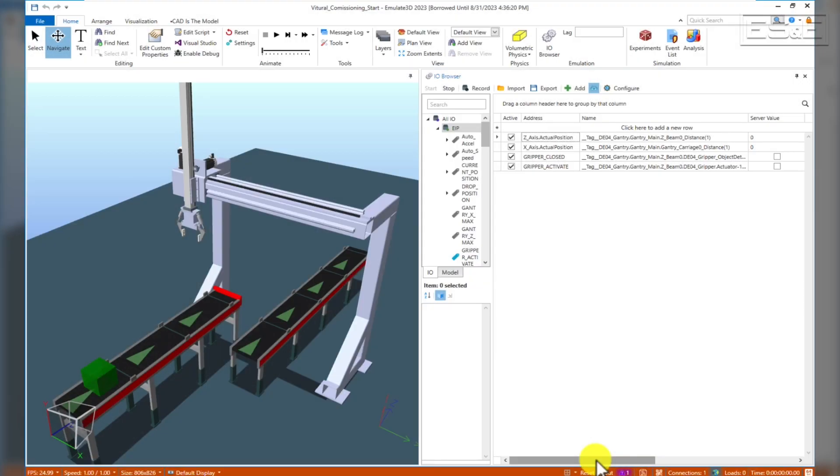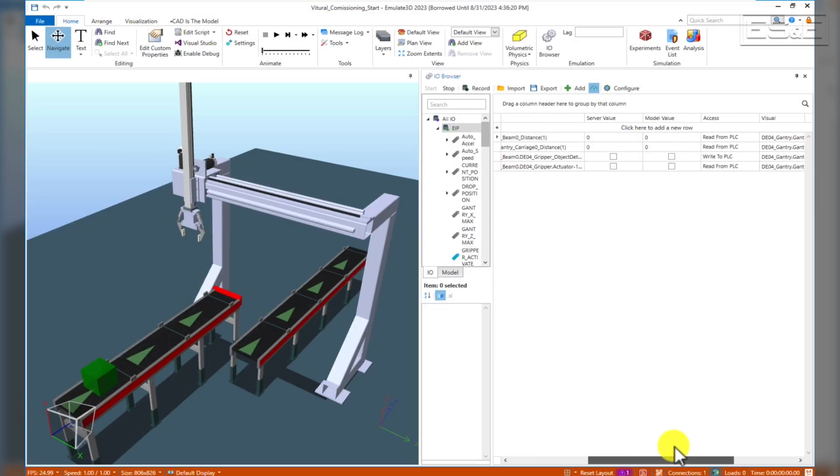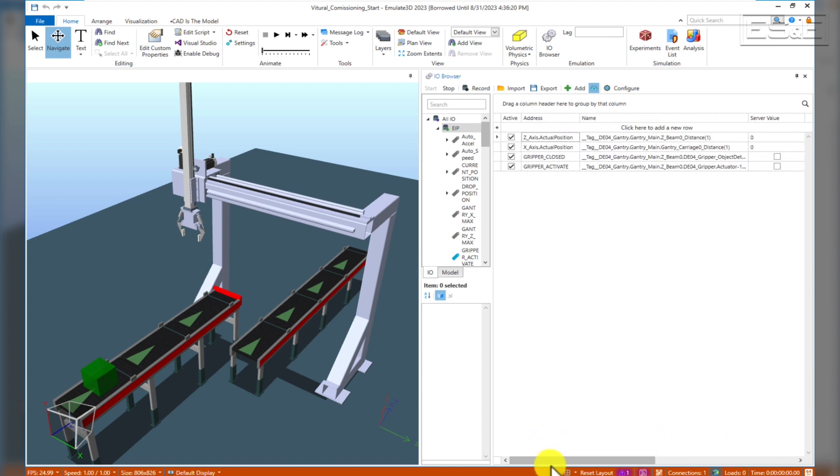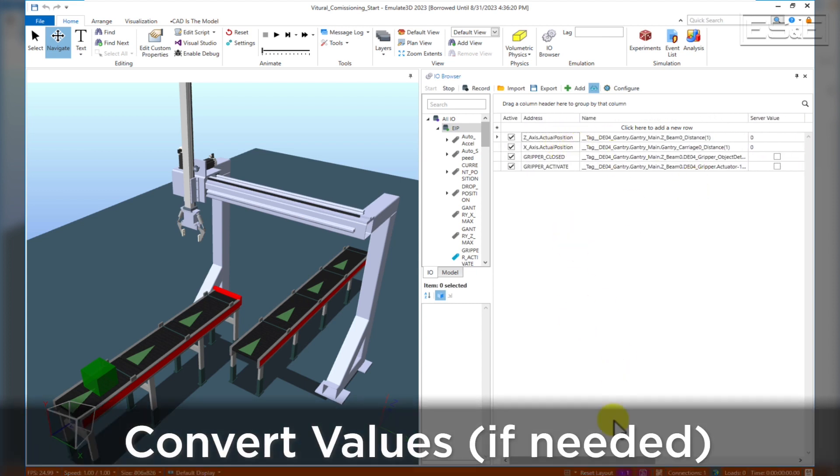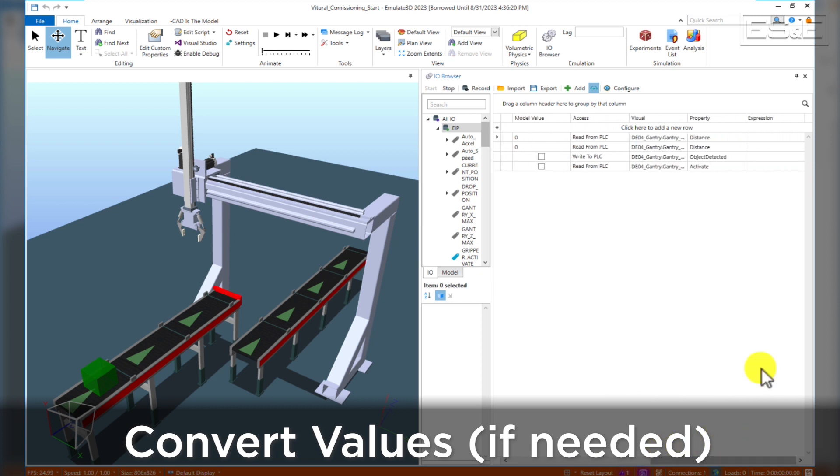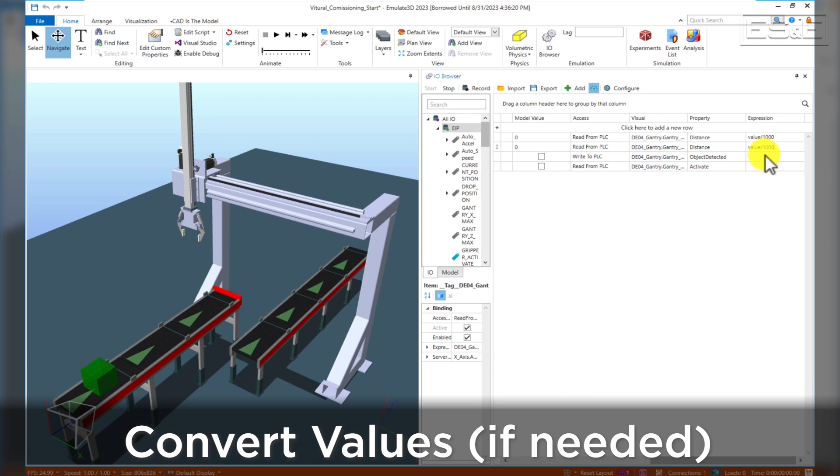For the position tags, Emulate 3D is expecting the values to be in terms of meters. The PLC is sending a tag in terms of millimeters. So we're going to have to do a quick conversion in the expression column to convert from millimeters back to meters for Emulate 3D.